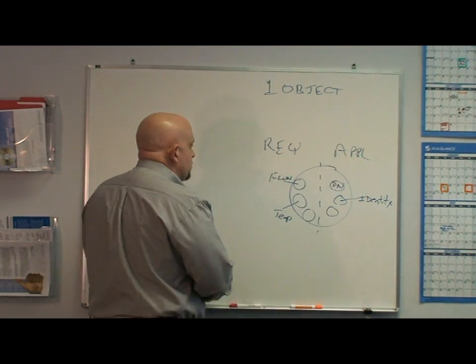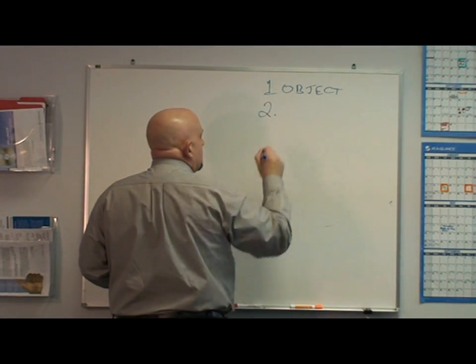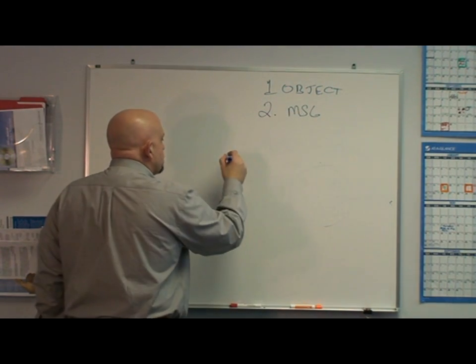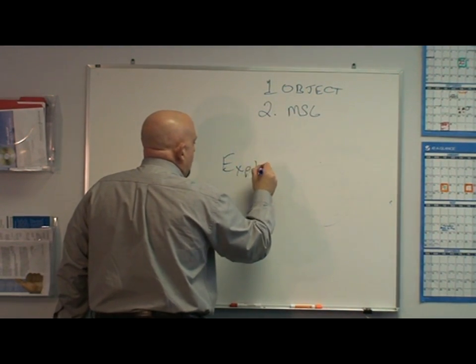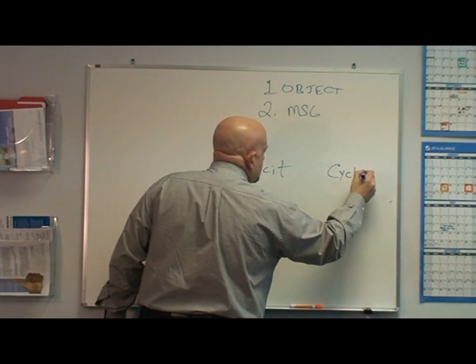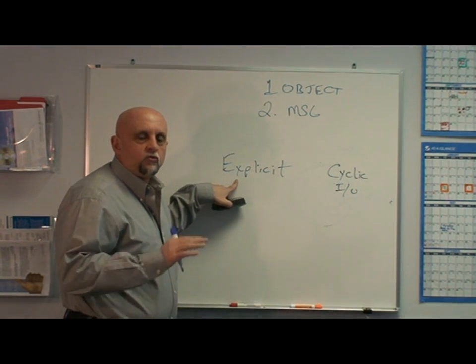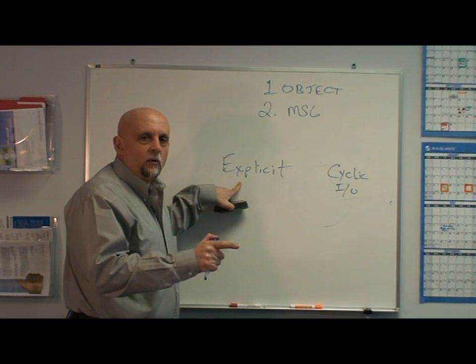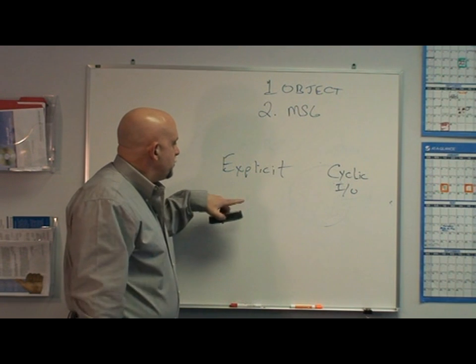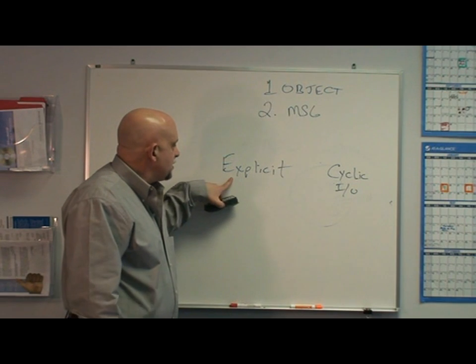That's number one. Number two is messaging. There are two types of messaging: explicit messaging and cyclic or I/O messaging. Explicit messaging is a message that goes right to the object and says, for example, 'I want to read or write object 64, attribute 2.' You can open up the packet and see what's in it — that's an explicit message.